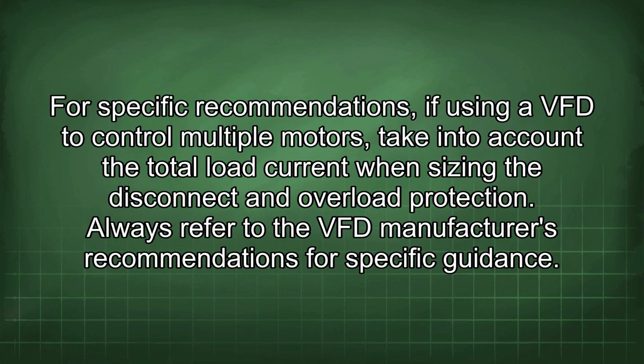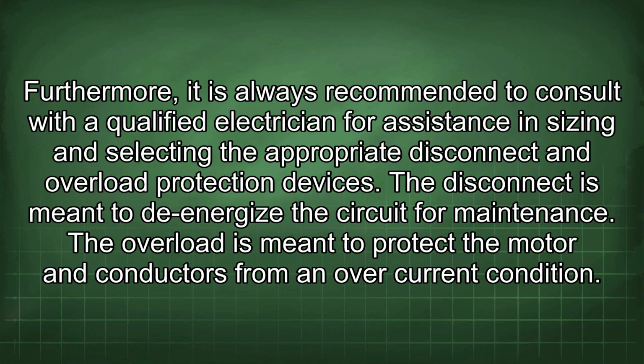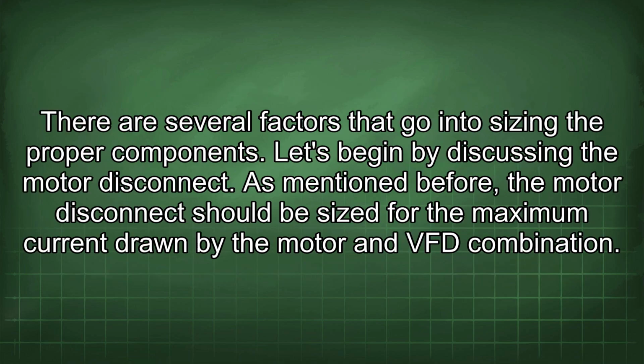For specific recommendations, if using a VFD to control multiple motors, take into account the total load current when sizing the disconnect and overload protection. Always refer to the VFD manufacturer's recommendations for specific guidance. Furthermore, it is always recommended to consult with a qualified electrician for assistance in sizing and selecting the appropriate disconnect and overload protection devices. The disconnect is meant to de-energize the circuit for maintenance. The overload is meant to protect the motor and conductors from an overcurrent condition.